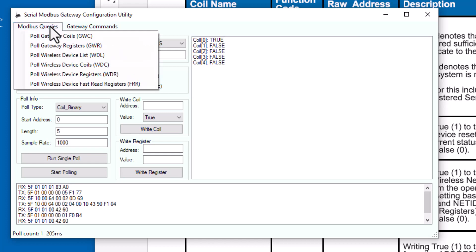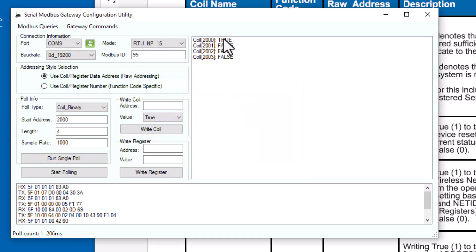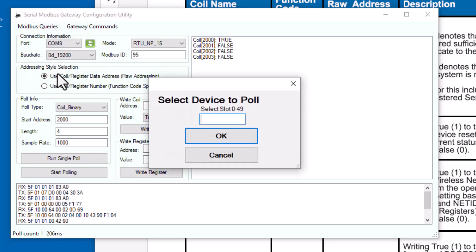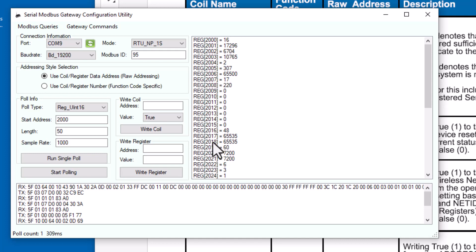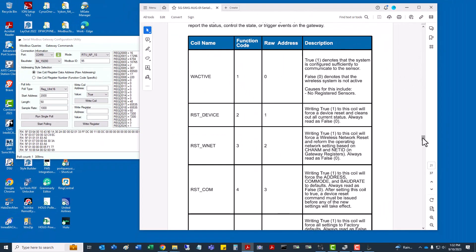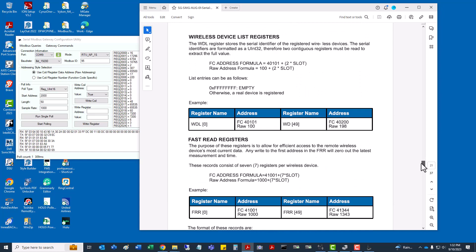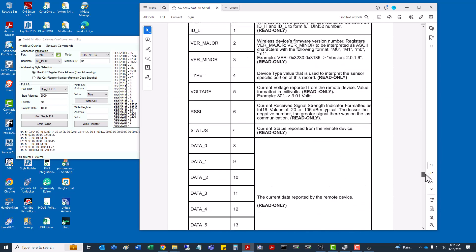I'm going to pop the battery inside the sensor. Go to Modbus Queries, Wireless Device Coils, our first index slot zero, clicking OK. Perfect, we've got data coming back on that. The user guide calls out what the different registers represent. So here I'm going to go to Wireless Device Registers, same thing, we'll select slot zero. Nice, now we got a bunch of data points that are actually being read off from the sensor showing the holding register numbers.